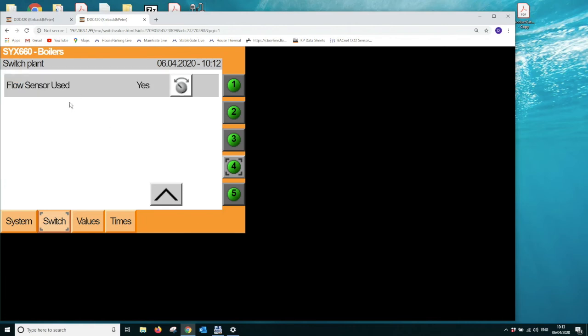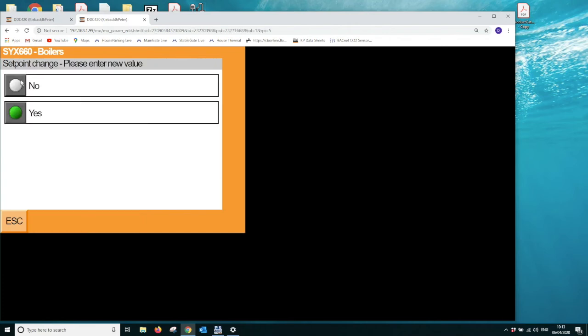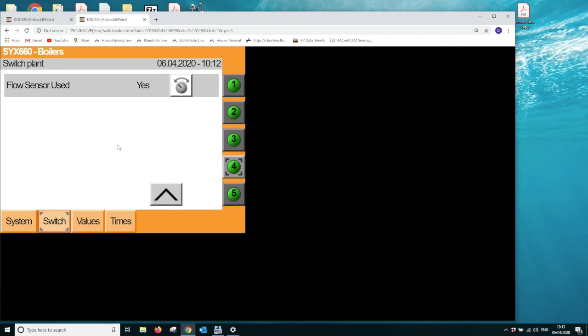The final option is if we have elected to use a boiler flow sensor. Now some applications may be replacing existing equipment, such as a DC1100, where that particular product did not necessarily have to have a boiler flow sensor. If you don't have one, you need to select this to be no. In our application we do, because that's the most efficient way of modulating the boiler output to match the loads. Okay.